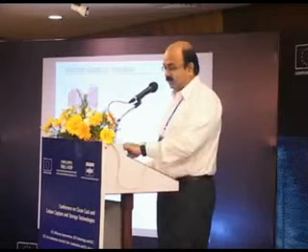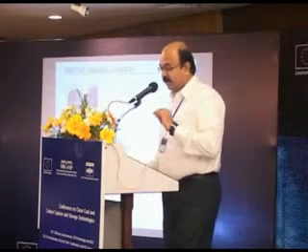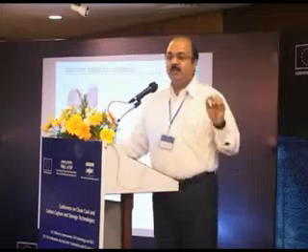So we also modularized the construction of the aerator. We changed the total aerator, we modularized it. Additional block means we put one more extra. It's not a basket, sir. If you see the picture on the right hand side bottom, they are tubular aerators, not a regenerative aerator. So we put one more block there on the right hand side. We had space constraints, but still managed to do it.